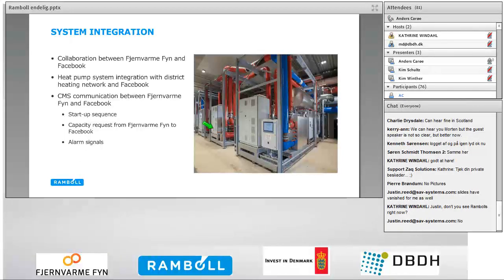Fjernvarme Fyn and Facebook have their own control and monitoring systems that are continuously communicating with each other. For example, Fjernvarme Fyn will send a startup request to Facebook when they want to start the plant after a period without operating. When Facebook then accepts this request, a series of events will take place before the heat pumps can start. This includes opening motorized valves and flushing the waste heat recovery circuit, since there might be large temperature differences in the overall system.